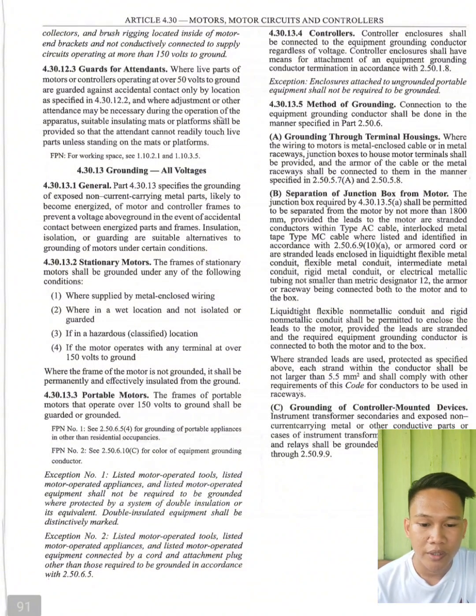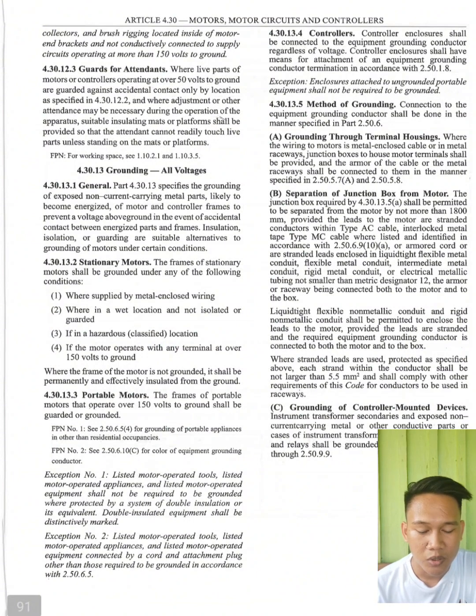So next, we have 4.30.13.3 Portable motors. The frames of portable motors that operate over 150 volts to ground shall be guarded or grounded. So, there are exemptions. First, listed motor-operated tools, listed motor-operated appliances, and listed motor-operated equipment shall not be required to be grounded where protected by a system of double insulation or its equivalent. Double-insulated equipment shall be distinctively marked. Second exemption: listed motor-operated tools, listed motor-operated appliances, and listed motor-operated equipment connected by a cord and attachment plug other than those required to be grounded in accordance with 2.50.6.5.